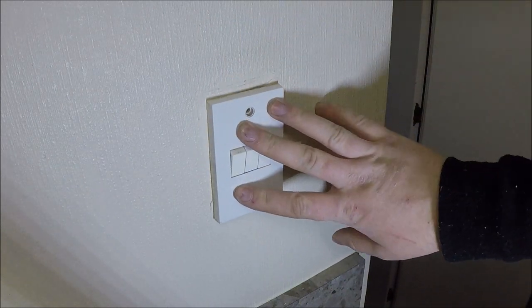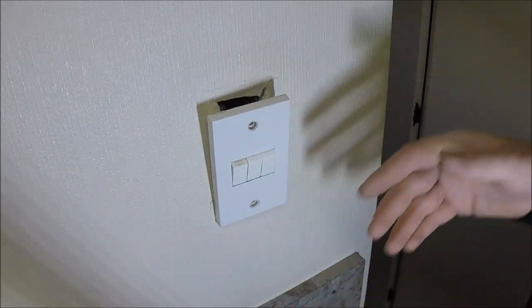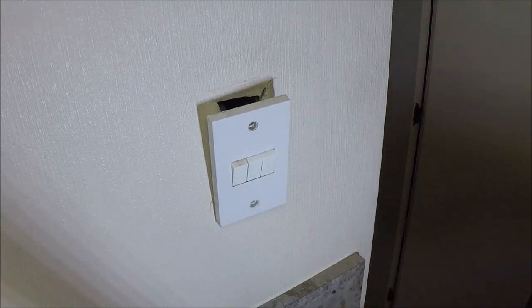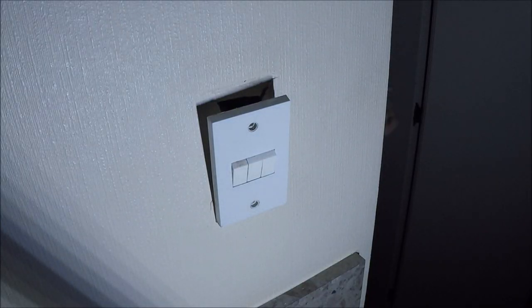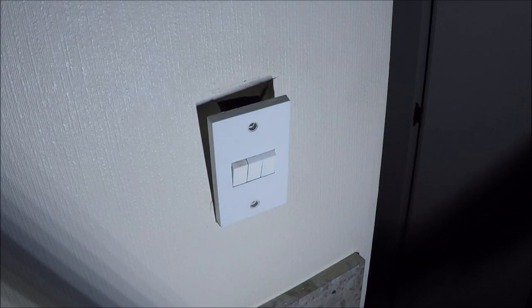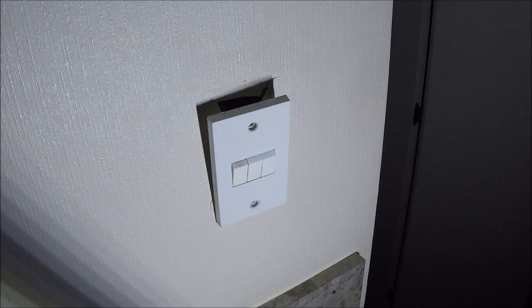Before you rip these off the wall you want to make sure the circuit's dead. So the best way to do that, whip all the lights on and pull lighting breakers out until they die. Just like that. And always double check.